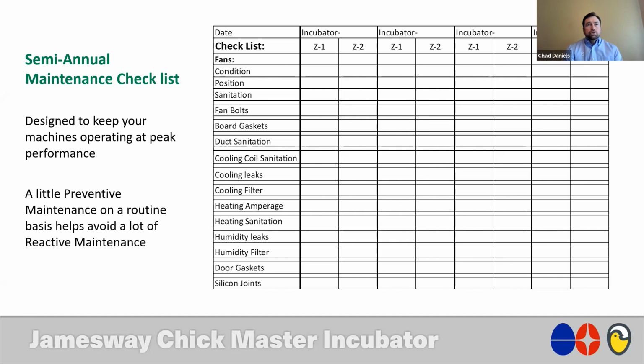If it does have the older, larger copper cooling coils, those can have a tendency to get a lot of buildup on them as well. So it's important to have that on your checklist. Also look for any leaks in the cooling system, such as where the tubing connections are, where it connects to the end of the coils. And then also I've got noted here a cooling filter. And what this is in reference to is actually the strainer that's on the chilled water supply service coming to your machine. Oftentimes this gets overlooked in some situations. It's something that hadn't been checked in several years, and you pull that filter out of there or that strainer out of there, and you see a lot of debris build up, which really just reduces your cooling capacity to the machine.